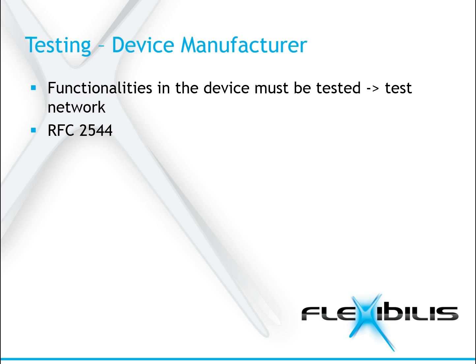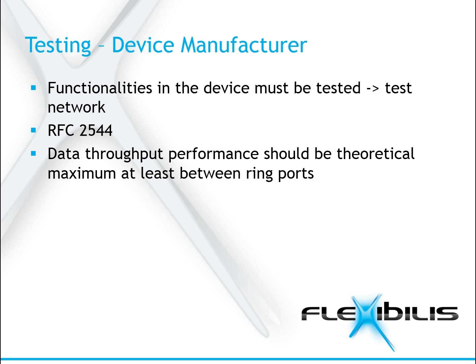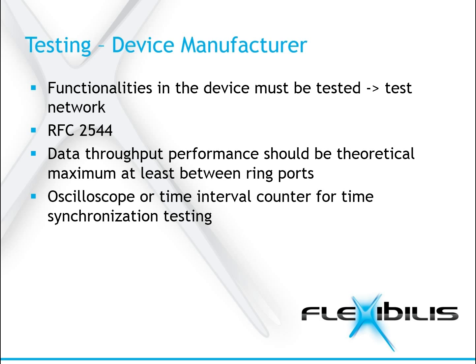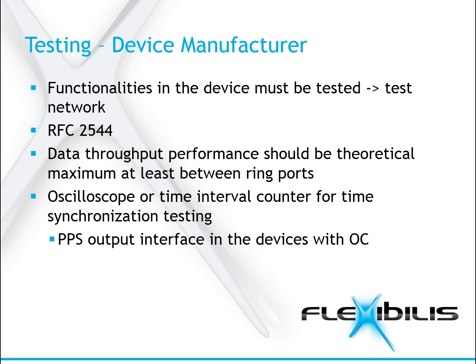As the data throughput performance of an HSR ring is the same as the throughput of the weakest performing device, the performance should be the same as the theoretical maximum at least between the ring ports. Time synchronization is most easily tested with an oscilloscope or a time interval counter if there are pulse-per-second outputs in the devices. Therefore, we would suggest implementing a PPS output interface in every device that implements an ordinary clock, at least in the device internal debug interface.